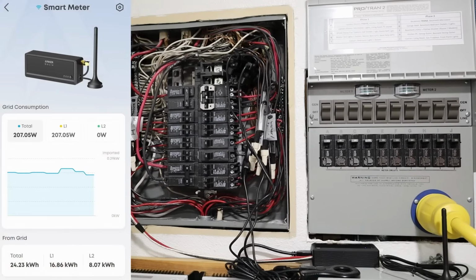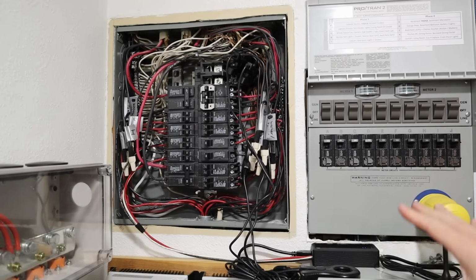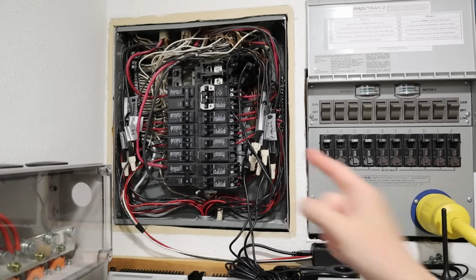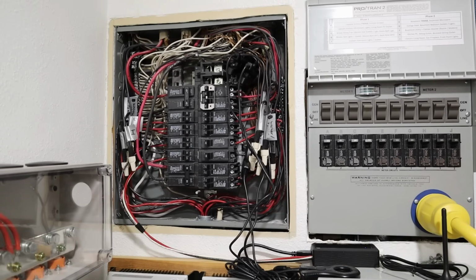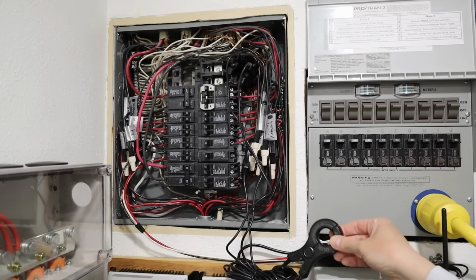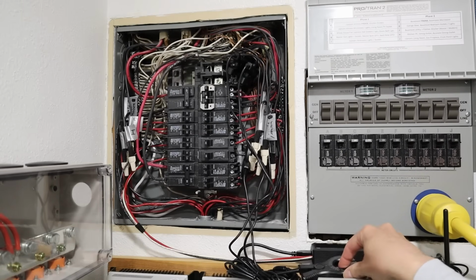For example, when you open the smart app, you can see the wattage for line 1 and the wattage for line 2. Now then what it does is it communicates to the F3000 that wattage and tells the F3000 to backfeed into the phase that it's connected into. Because the F3000 is only connected up to one circuit breaker, it's a 120 volt circuit breaker, it will only backfeed into the phase that it's connected into. That's why they allow you to connect up 2 F3000s, so you could backfeed into both phases.